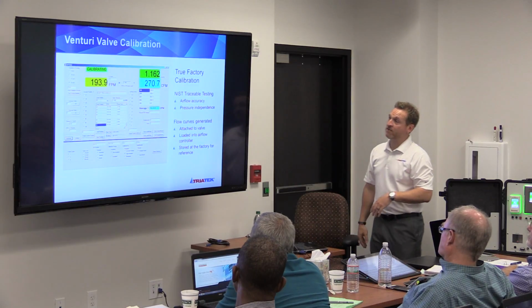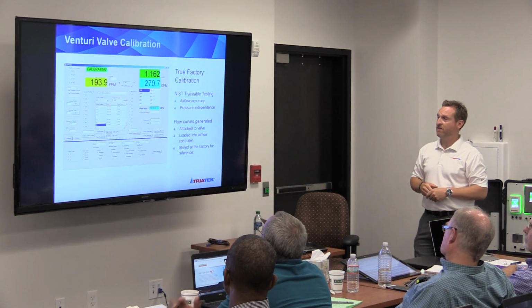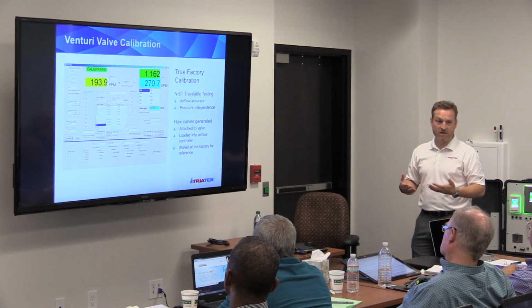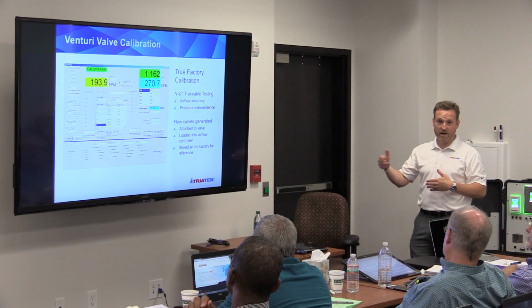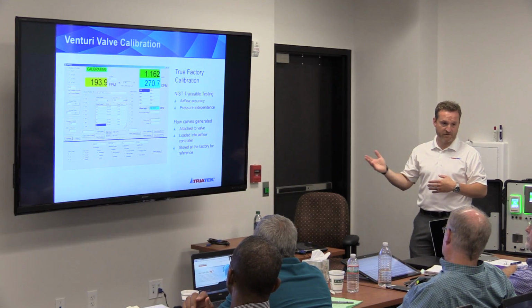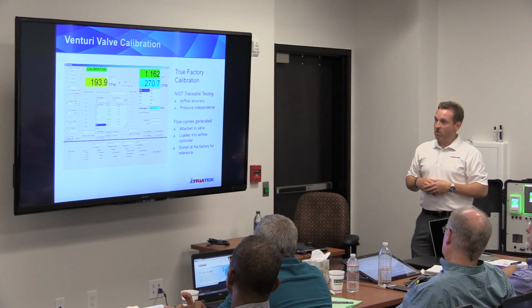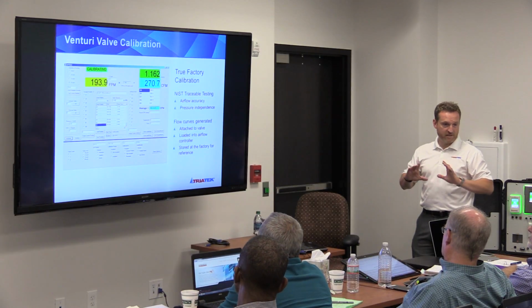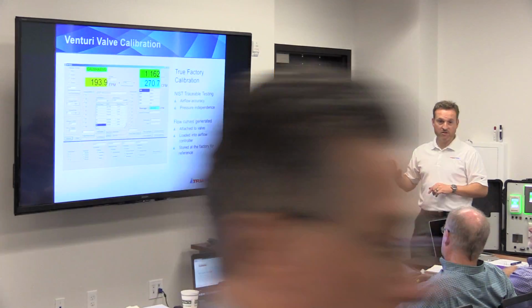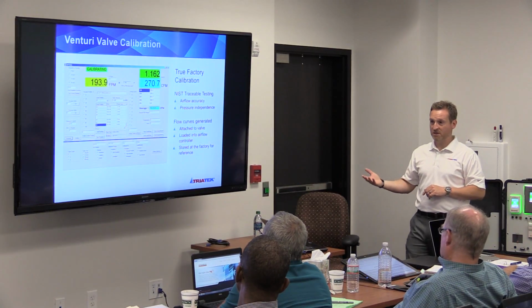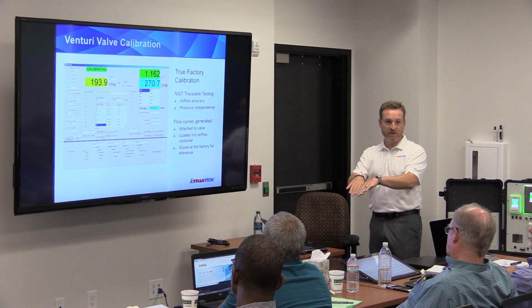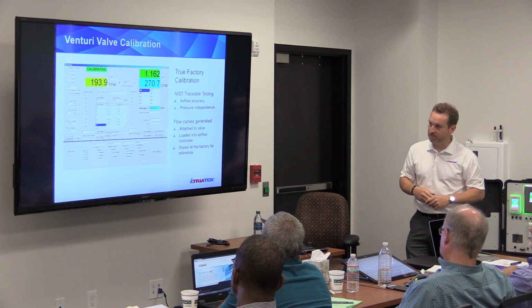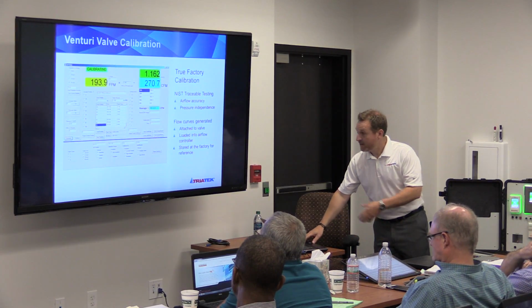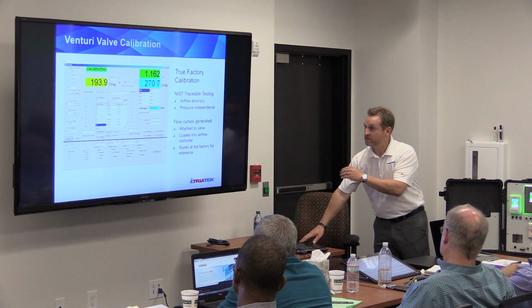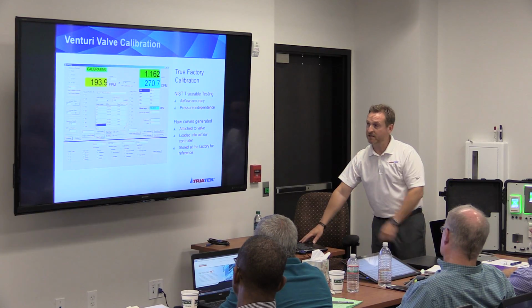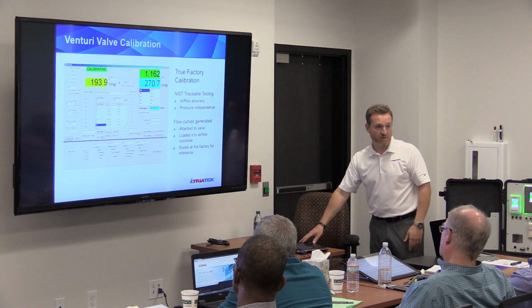This is a screenshot of our factory calibration station for our valves. As I said, all the valves are tested for airflow accuracy and pressure independence throughout the full range of each valve. The flow curve for each valve is attached to the valve on a label, and it's also stored at the factory. If there's a controller associated with that valve, it's put into the controller calibration as well. And every one of our products is third-party validated using traceable instrumentation as well.